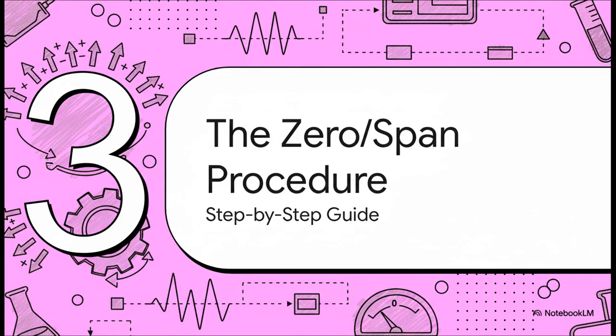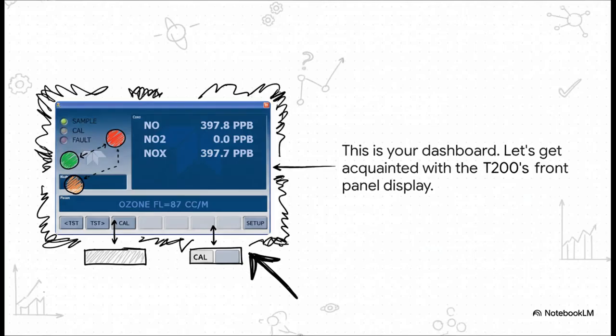Time for the main event. Let's walk through the actual zero and span calibration using the front panel of the analyzer. So this screen right here, this is your command center for the whole operation. You've got your real-time numbers right in the middle, status lights over on the left, and your menu buttons down at the bottom. We're going to be getting friendly with that cal button in just a second.